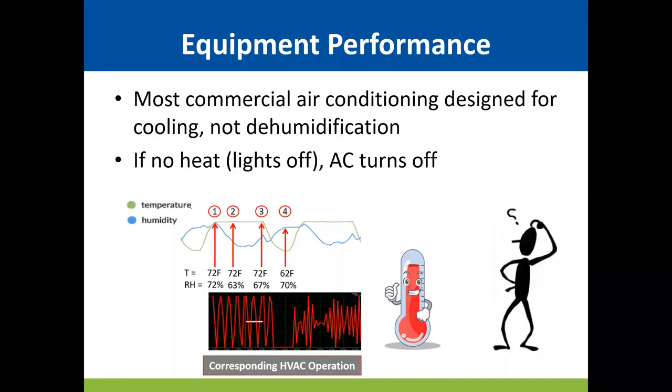So in terms of equipment performance, most commercial air conditioning equipment is designed for cooling, not dehumidification. So you're humming along, the lights are on, you're like, oh yeah, like we're able to control humidity and temperature and things are going well. And then the lights turn off.